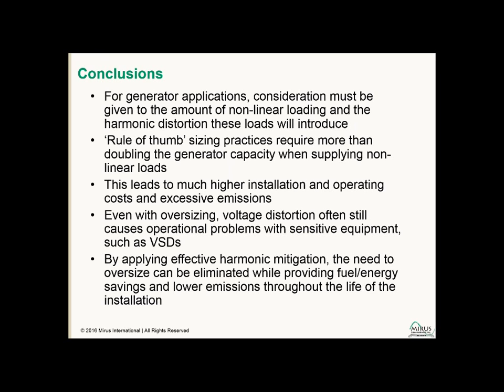Even with oversizing, you can still have voltage distortion levels that can cause operational problems, as we did in this pumping application. But if we apply effective harmonic mitigation, the need to oversize can be eliminated, and therefore we can provide significant fuel and energy savings and lower emissions throughout the life of the installation.